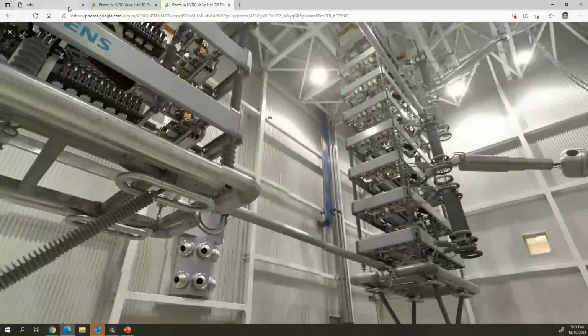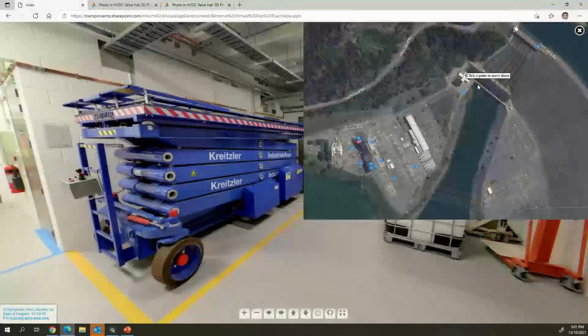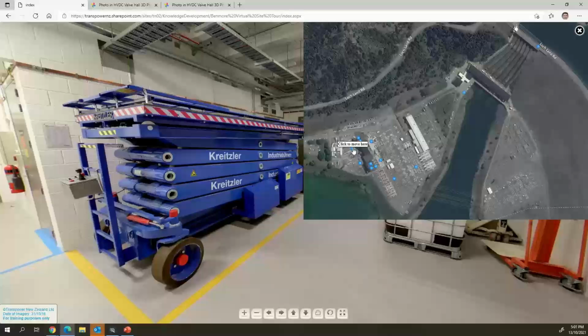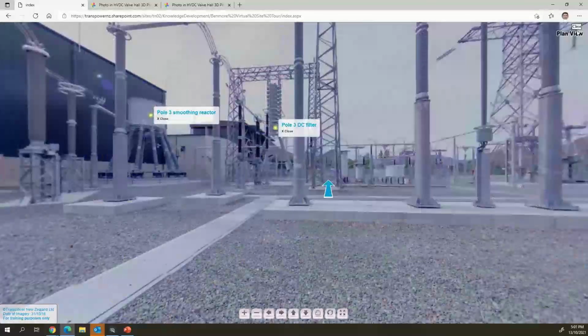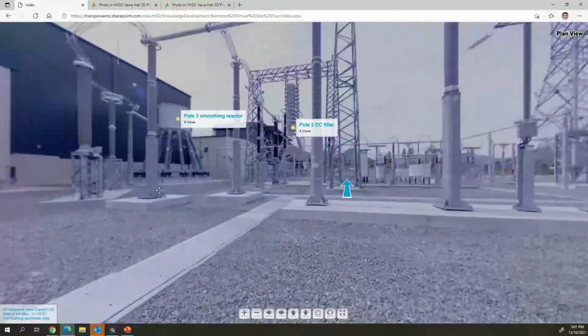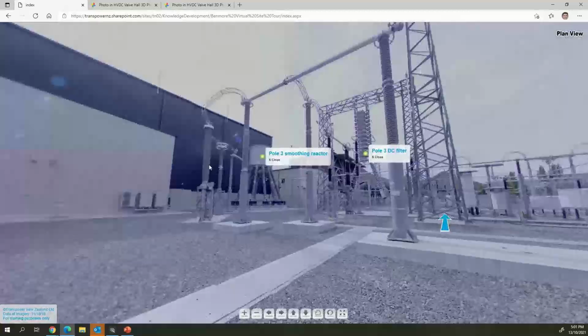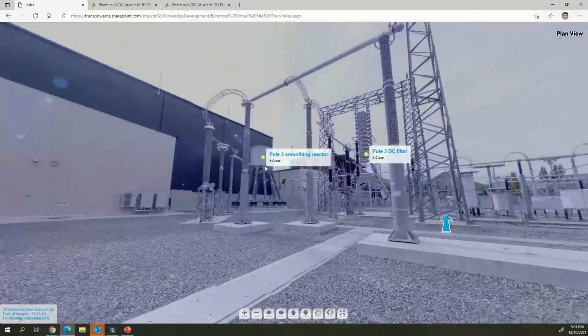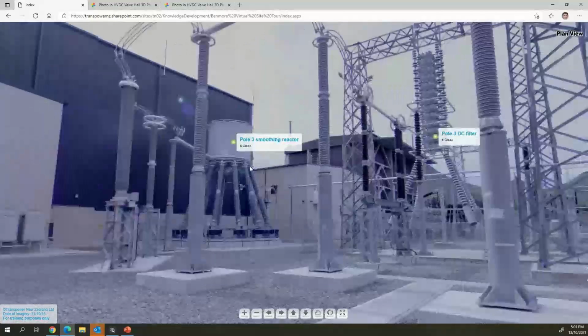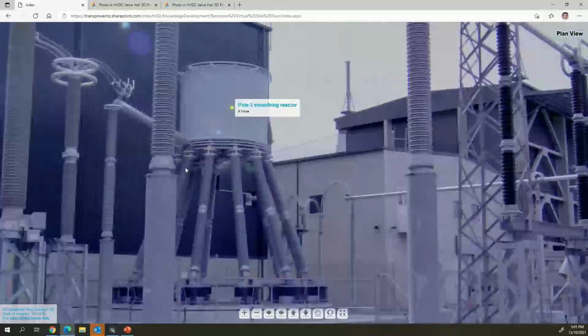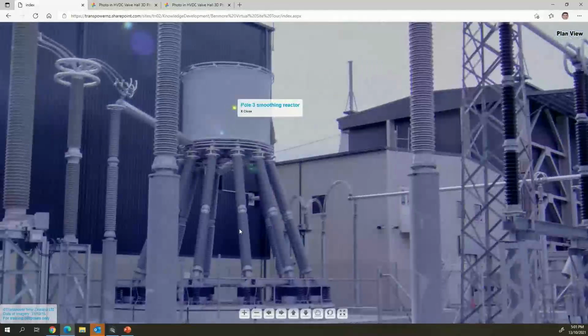Cool, so we'll just go out to the DC side, into the DC yard. So this is pole 3. So the high voltage DC bushing's behind the smoothing reactor. You can't quite see it there, but there's the smoothing reactor. You can see our one's definitely got a bit more burly design for the seismic with the thicker insulators, and it's a bit more squat, and it's also got this rocking base for the seismic issues.